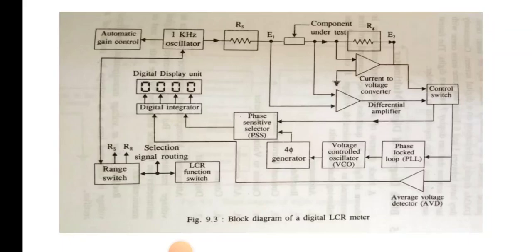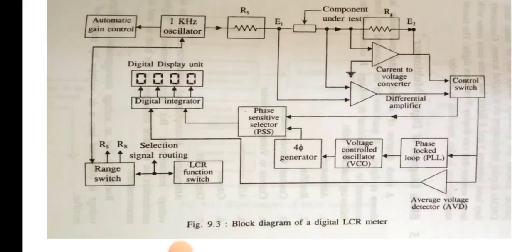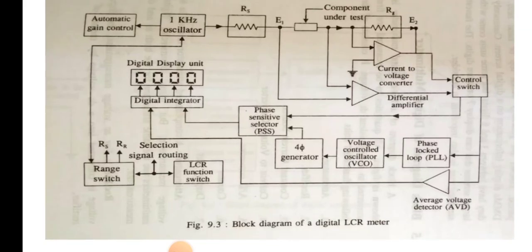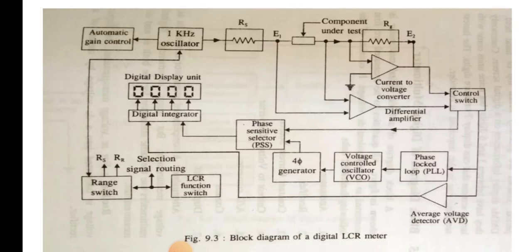The component to be measured is selected by the three-way switch, also called the LCR function switch, located at the bottom right side next to the range switch. This switch is used for the selection of the desired function. The working principle used in the LCR meter is to measure the voltage across the component under test.